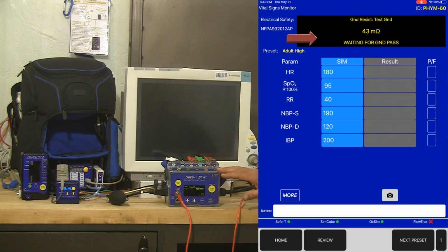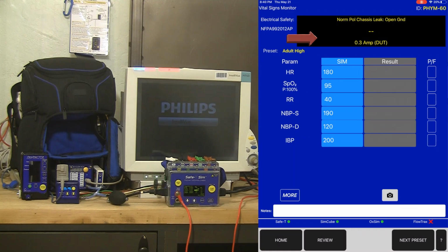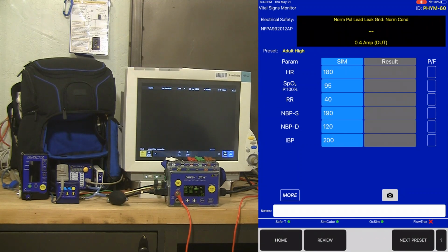We've got an electrical safety test started from the iOS device and that Bluetooth connection, and we can actually see real-time the results coming back for that electrical safety test. So just by hitting that start key, we've taken control over all the test equipment that you see here, the electrical safety analyzer, the SimCube NIBP simulator, and the OxSim SpO2 simulator.